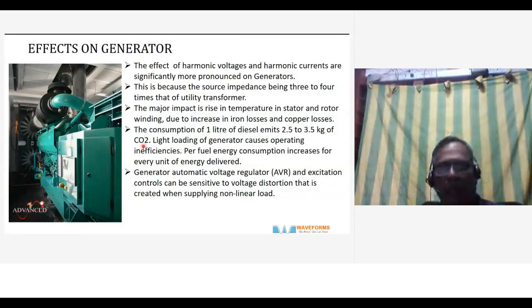So the generator automatic voltage regulator and excitation controls can be sensitive to the voltage distortion that is created in supplying non-linear load. So in a harmonics-rich environment, the generator can have serious problems with the AVR also. So operation can flip. So these issues are being faced by many industries.